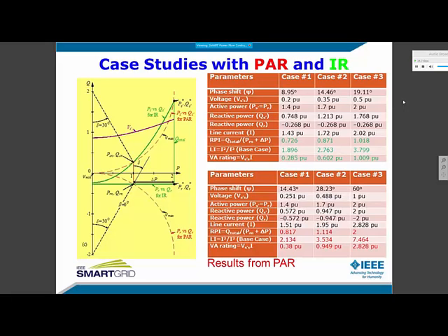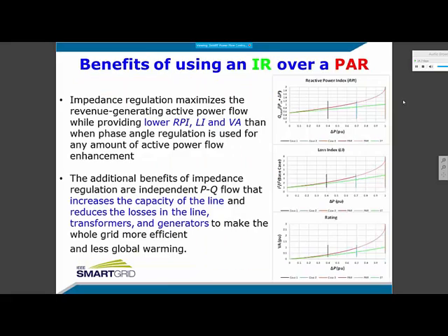In addition, the impedance regulator can be operated at no additional Q demand from the load. Whereas in a phase angle regulator, you see the Q demand from the load side increases as well as the source side when the demand for active power increases. Now, the impedance regulation also maximizes the revenue-generating P flow while providing a lower RPI, lower loss index, and lower rating than when a phase angle regulator is used for any amount of power flow enhancement. The additional benefits of impedance regulation are independent PQ flow that increases the capacity of the line, reduces the losses in the line, transformer, and generator, and makes the whole grid more efficient and reduces global warming.